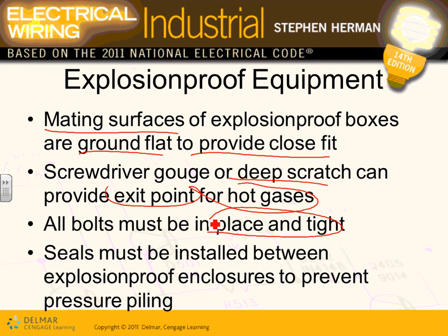Seals must be installed between the explosion-proof equipment to prevent pressure piling. There's something called pressure piling, guys. If you have two enclosures tied with a pipe, Adam, and you have an explosion in one and that gas goes into the second one, it will double the amount of pressure in the second one and have a bigger explosion. They call it pressure piling.